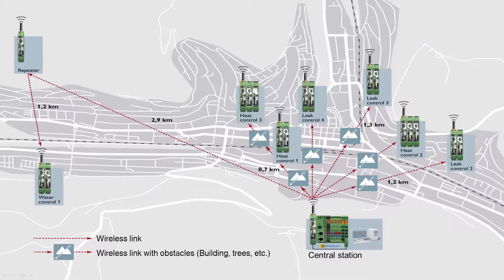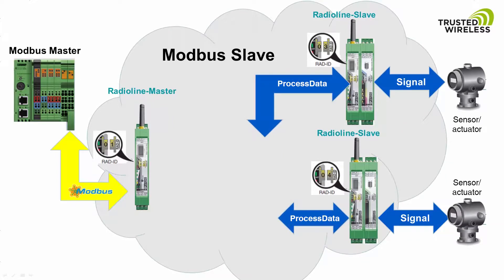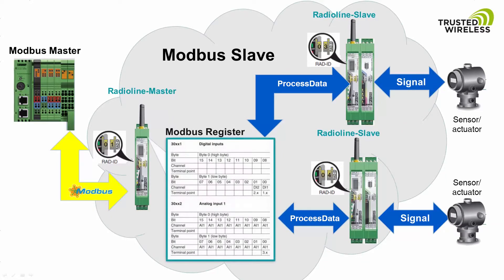In this mode, the complete Radioline network works as a Modbus slave. The process data of all I/O modules installed in the Radioline network are stored in a central Modbus table in the Radioline master. One wireless network can contain up to 99 I/O modules. If more I/O modules are needed, you can simply install additional Radioline masters or use the PLC Modbus RTU dual mode. The I/O data is converted to the Modbus protocol and stored in registers based on the I/O map address of the I/O module.